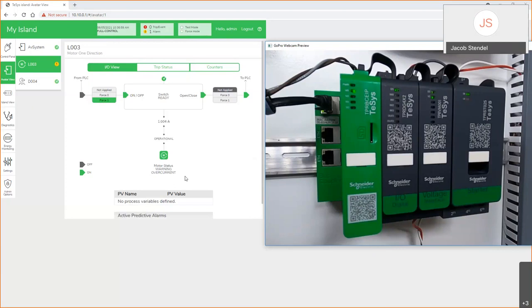But now you're running, now you're really pulling too much power. Now we're hitting that 1.2 amp area, and I just tripped. Now I have an overcurrent trip, but I have it configured to try again. This is an auto reset feature that you don't get with any other contactor system. Now the current's re-leveling back out, and we're going to approach the normal operating level. Now we're at 0.7 amps and all is well.